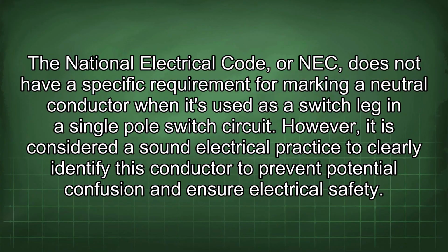The National Electrical Code, or NEC, does not have a specific requirement for marking a neutral conductor when it's used as a switch leg in a single-pole switch circuit.